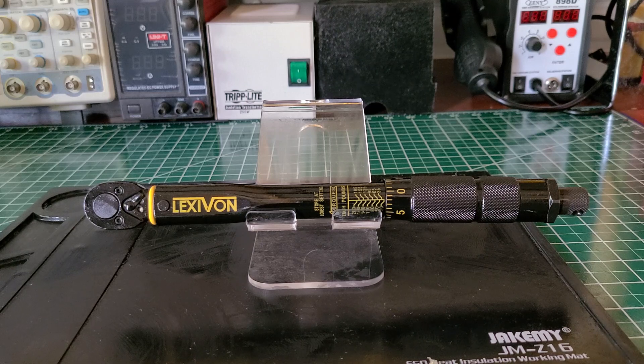This torque wrench — you may ask, why do I need one? A torque wrench is needed so you won't over-tighten something. In the electrical field, there is a code that requires you to use a torque wrench to tighten screws at your terminals, even the terminal lugs where incoming power comes in. It's in the NEC. Some people think tightening as hard as they can is fine, but that can cause the wire to overheat or break the lugs. There's a rated amount of torque you must apply to keep things working properly.